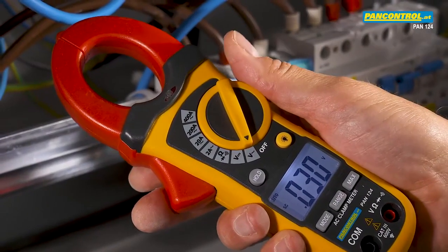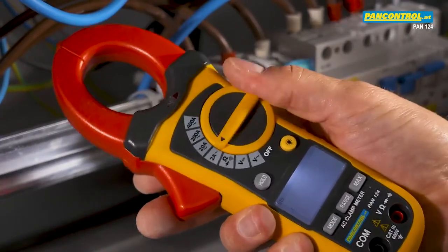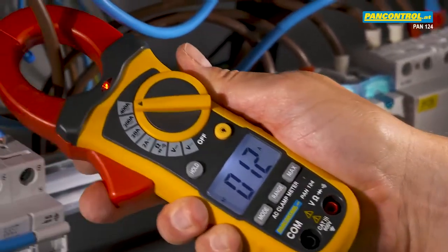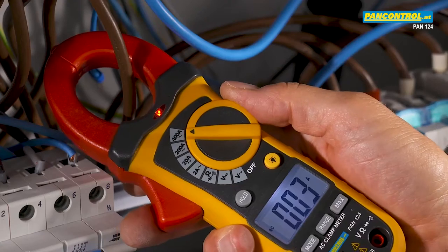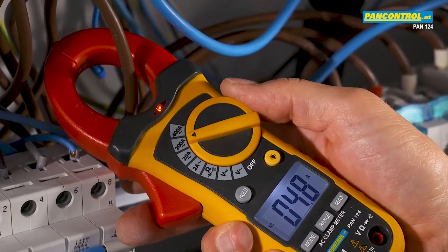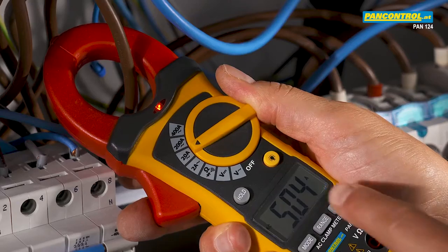When measuring unknown amperage, the highest range should be selected. When the displayed value appears too small, a lower range should be selected until the highest resolution is achieved.